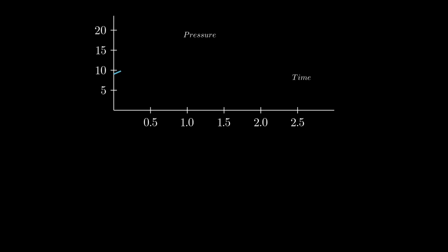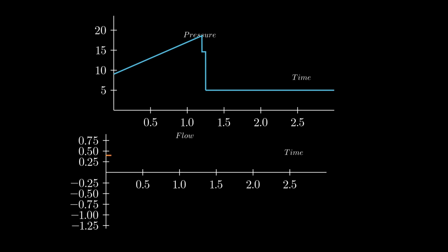To further understand the equation of motion, let's plot the pressure time curve and the flow time curve. To delineate the resistive from the elastance component, an end inspiratory breath hold is applied for a brief period, typically 5 to 10% of the total breath cycle. This pause reduces inspiratory flow to zero, allowing the airway pressure to equilibrate with alveolar pressure, the plateau pressure.